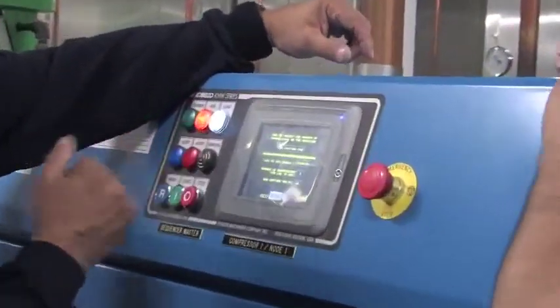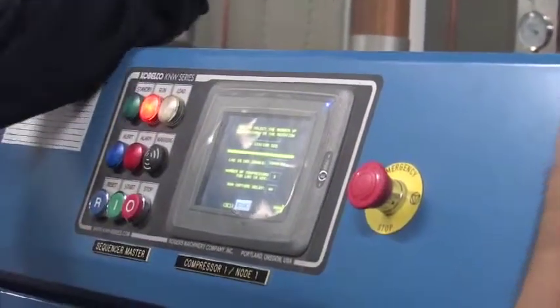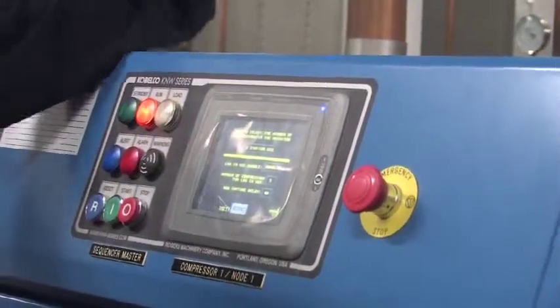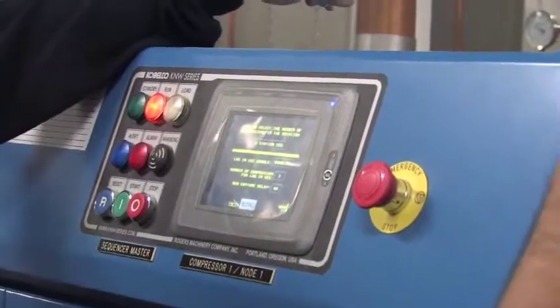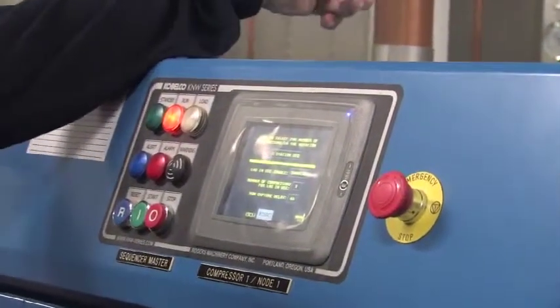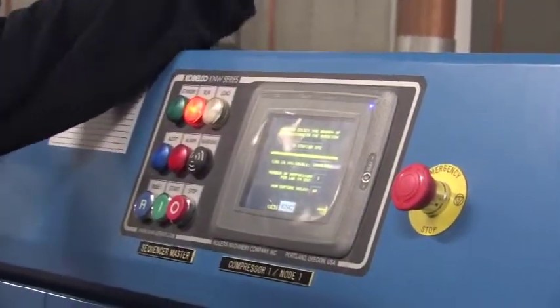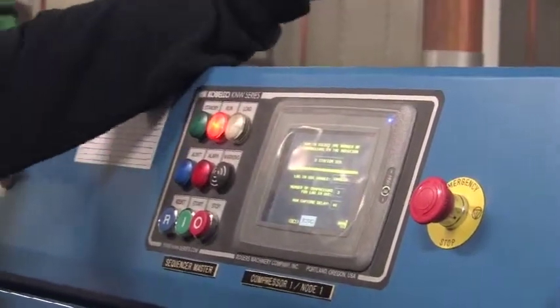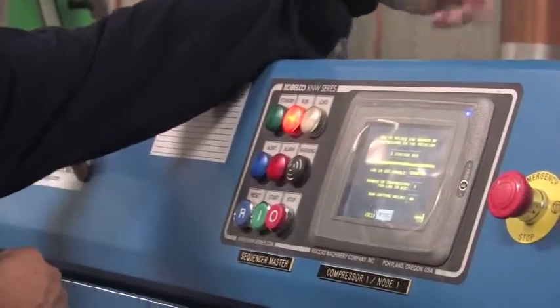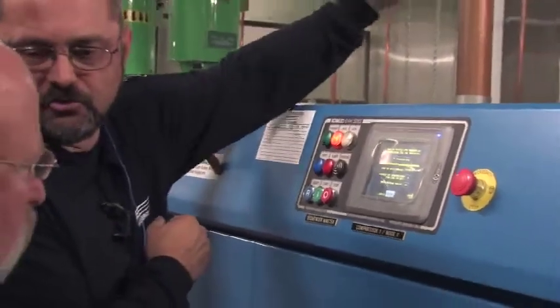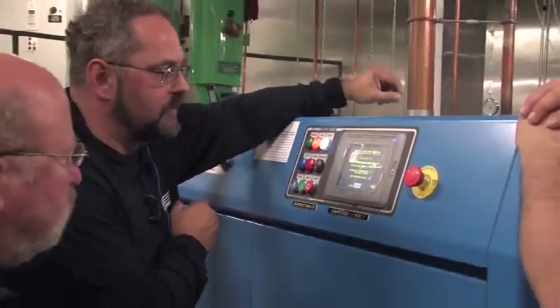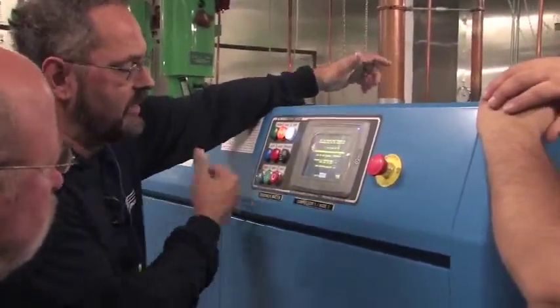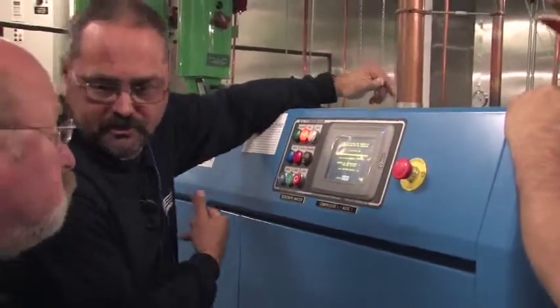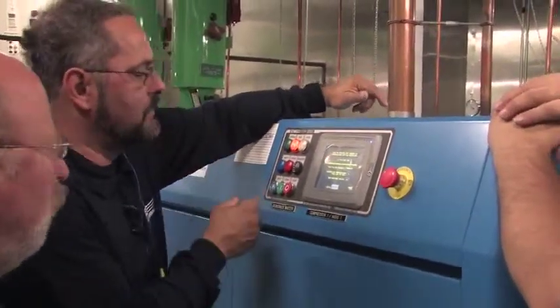Now, obviously, one of the things you can do with this: if you had a machine that was going to be out for a couple of weeks, you could come in and tell it it's a 2-station sequencer, and just make sure you have a direct wire connection to the machine that is going to be on. You know, the direct run to the Ethernet from the switch in that one to the switch in this one, rather than a daisy chain or whatever. But then you can fold it into being a 2-unit sequencer.